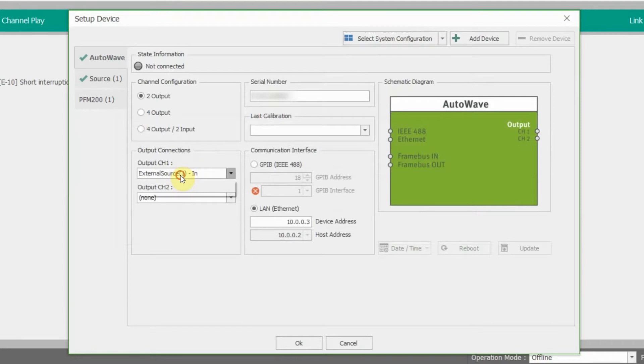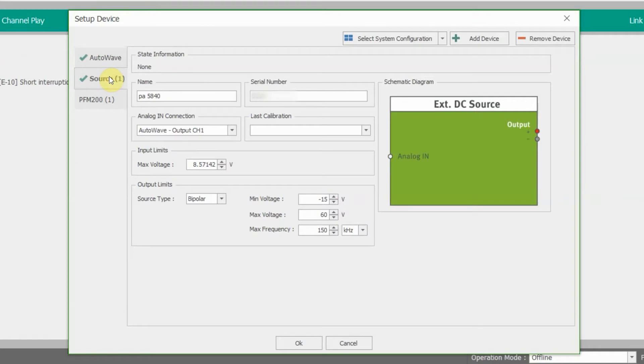If you look over here, output channel one. As we spoke about previously, we have that BNC connector going from our PA5840 — this is going to our channel one for EM TEST AutoWave. So you see that indicated there. Our LAN right here is another area you want to pay attention to. Our host address is 10.0.0.2. Our device address is typically going to be one less or one more than that — today ours is 10.0.0.3. You'll see our source right here, where we entered our PA5840 information. You'll see our source type, our min voltage, our max voltage, and our max frequency, all determined by our PA5840.